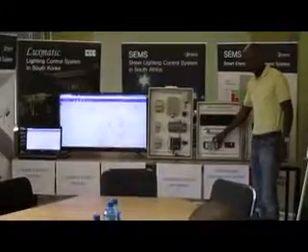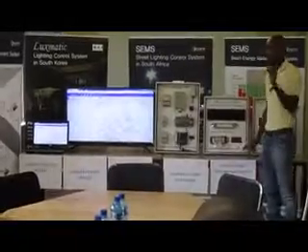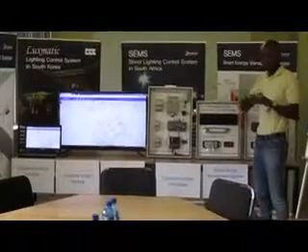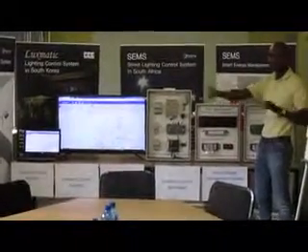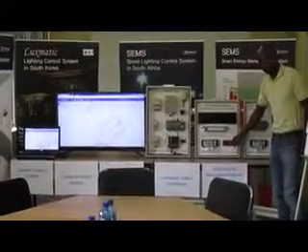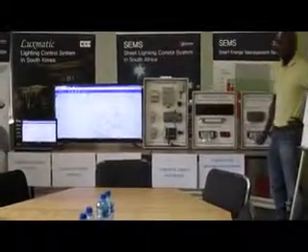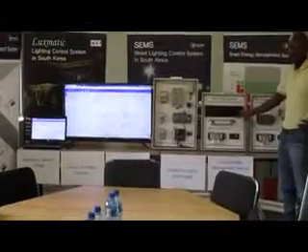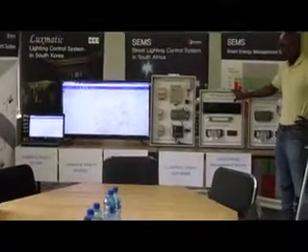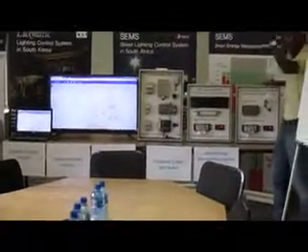Each lamp has this controller with a unique ID. So each lamp is going to have its ID, which we enter when we are programming. It helps the communication take it to digit number. This one is just a display, a voltage display and a current display. When I switch on, we're going to see how much power the fitting withdraws. Normally it's a 32 watts LED fitting. Now this one is the normal HPS that we use mostly everywhere.